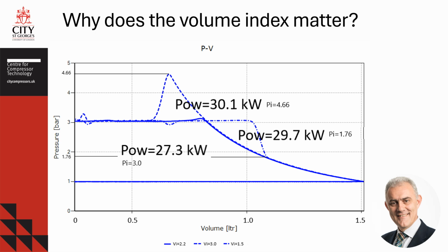Therefore, for an optimal efficiency of a compressor, it is important to adjust the port to achieve minimum power consumption. In addition, the increased pressure within the compressor will create high bearing loads, which will reduce bearing life and reduce reliability.